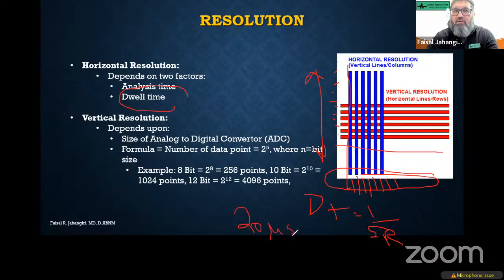And that is your CNIM exam question. They say, okay, you cannot have a distance of more than 20 microseconds. That's the maximum allowed for any machine to record evoked potentials or spontaneous EEG. So anything less than 20 microseconds is fine, but a distance between the horizontal points of more than 20 microseconds will distort the signal.